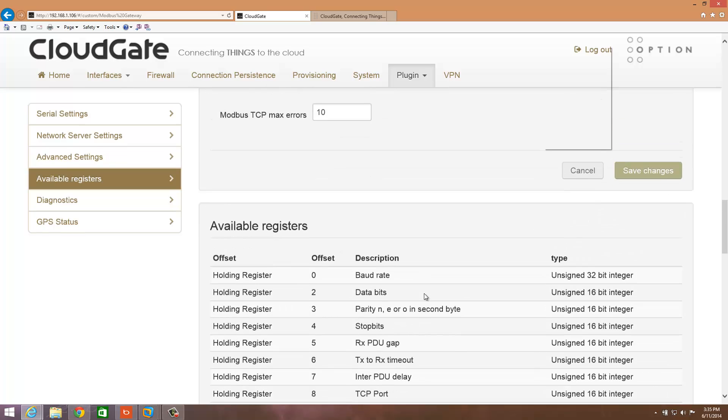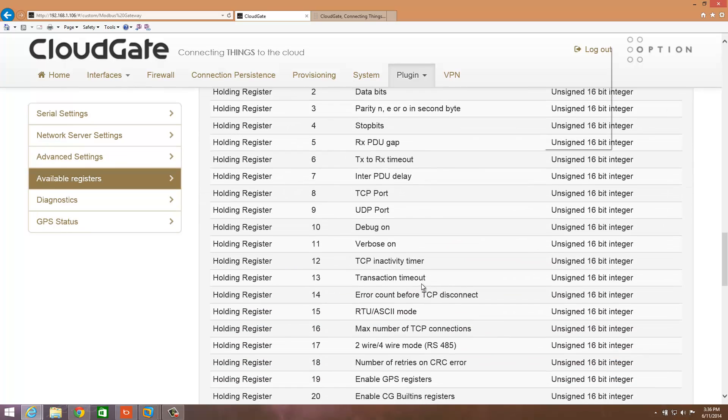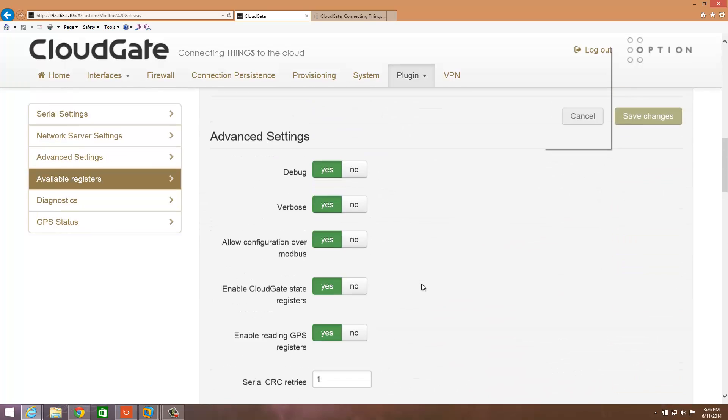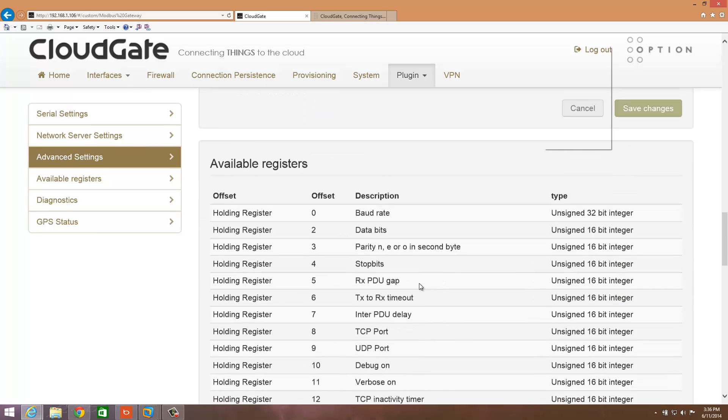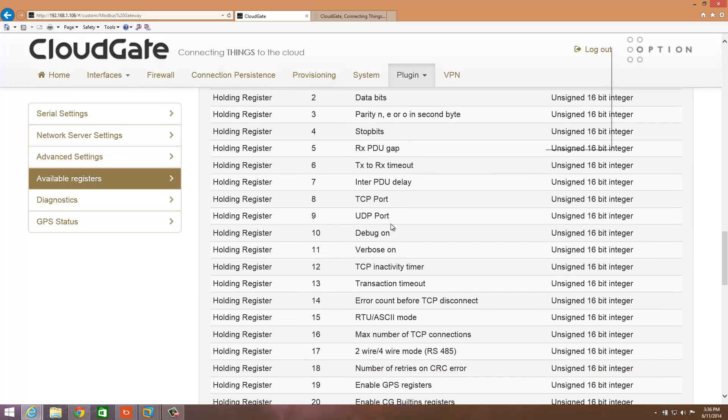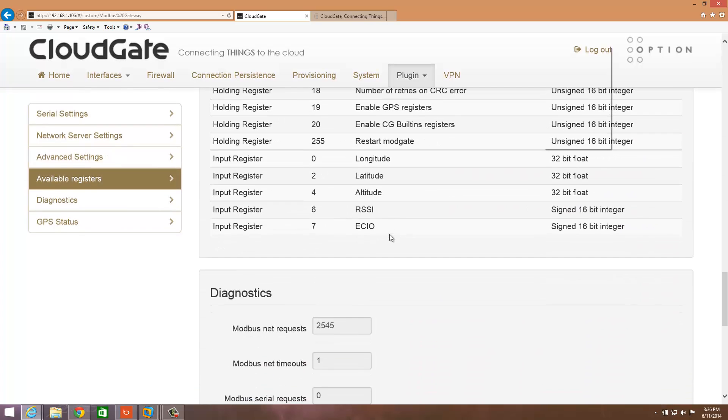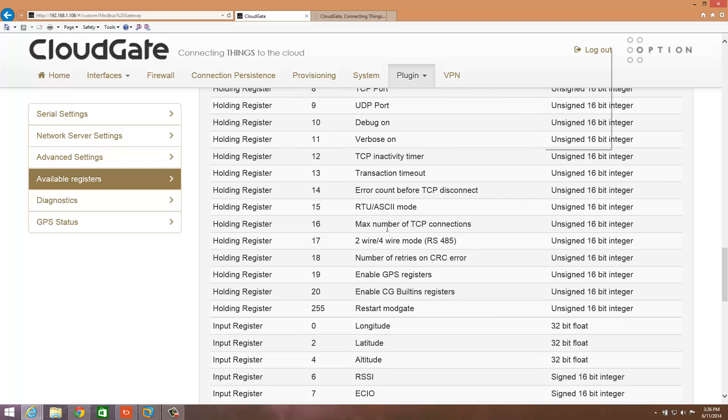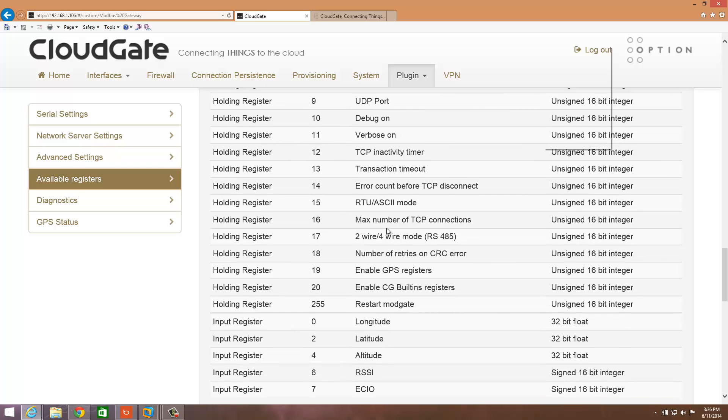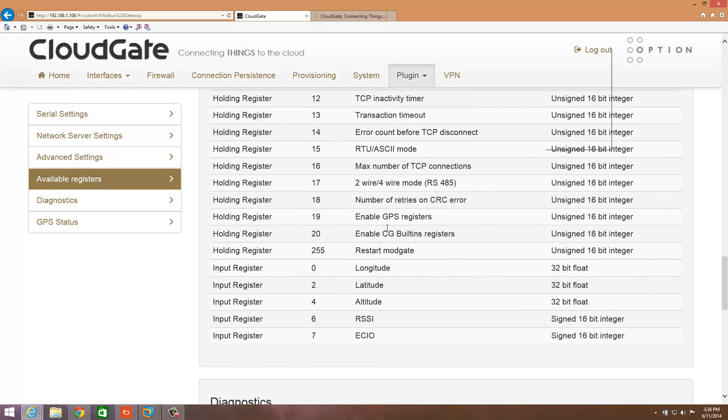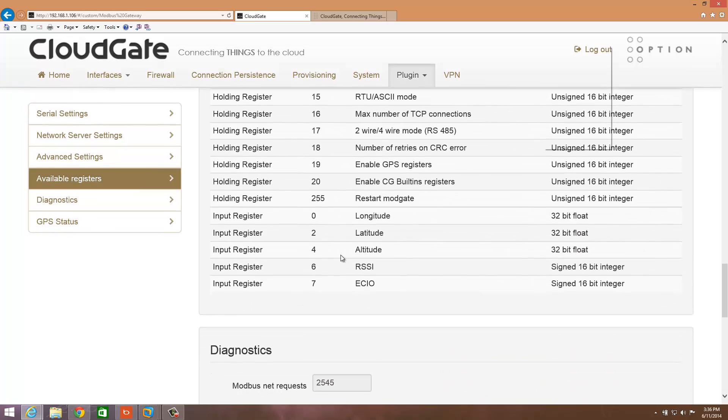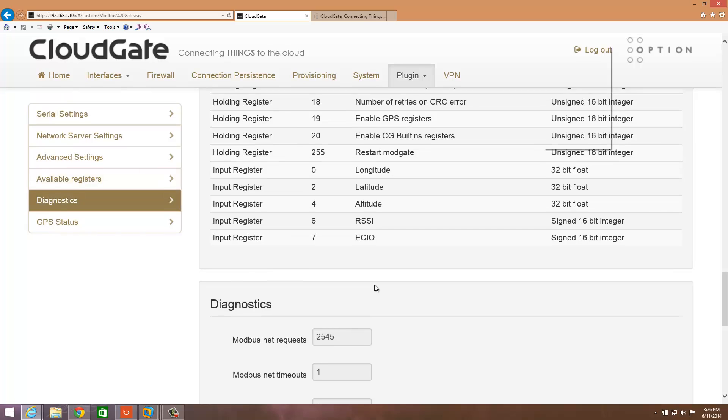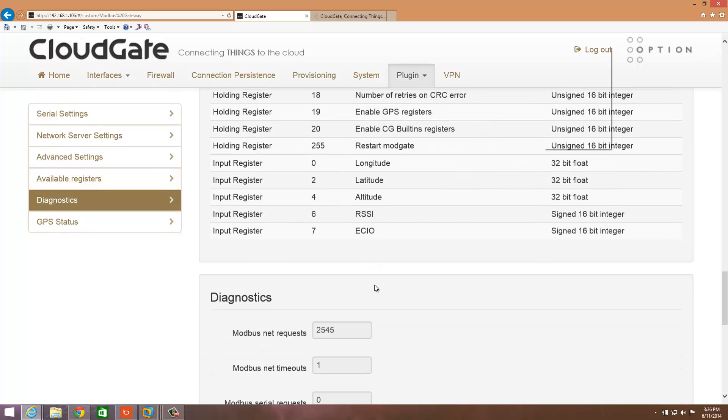If everything's correct, what you should see is some of this information here. If you're going to do configuration, there's a check here that allows configuration over Modbus, and then that will open up all these as Modbus holding registers and input registers. Here's the main registers we're interested in, which is longitude, latitude, altitude, your RSSI, which is signal strength, and then ECIO, which is another type of signal strength.